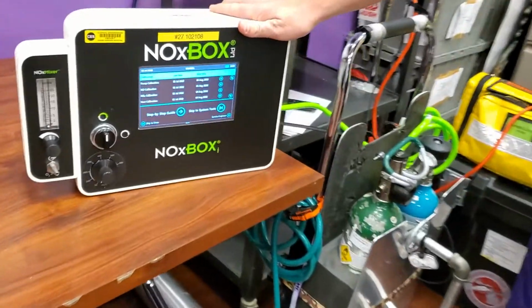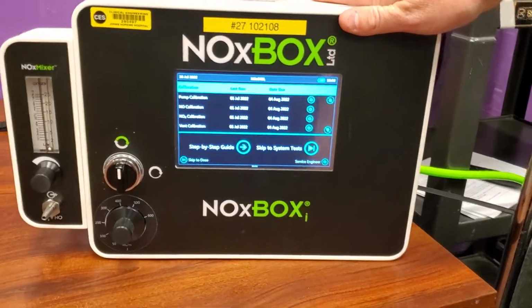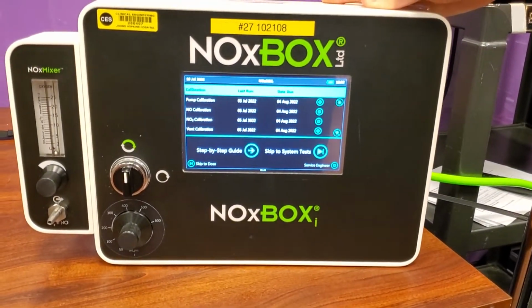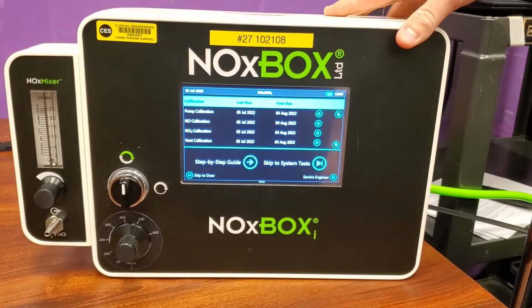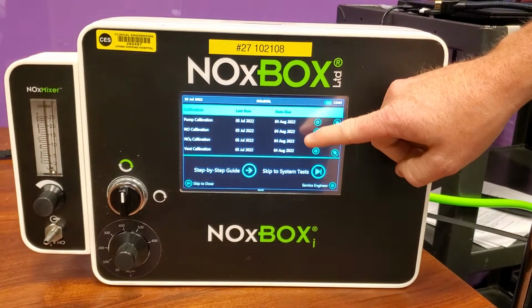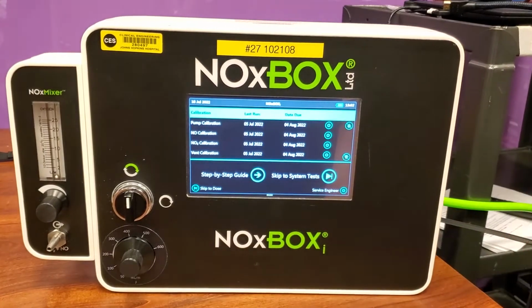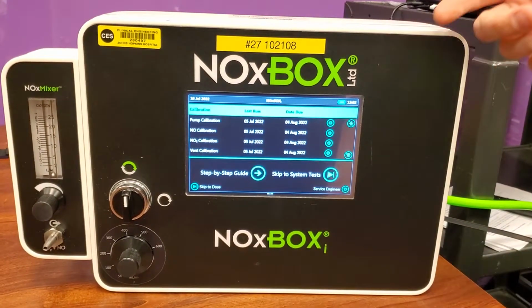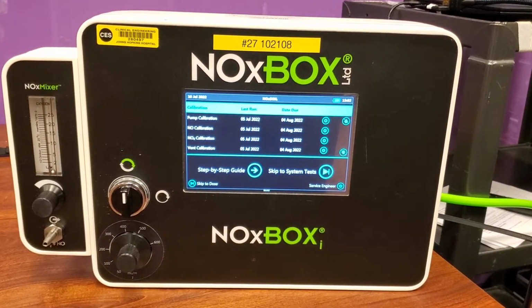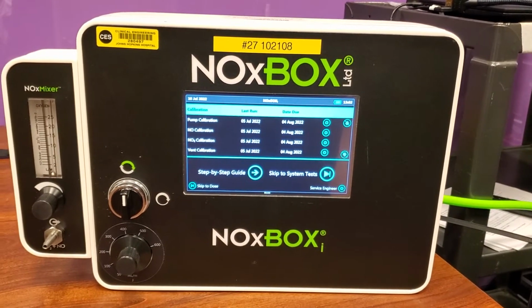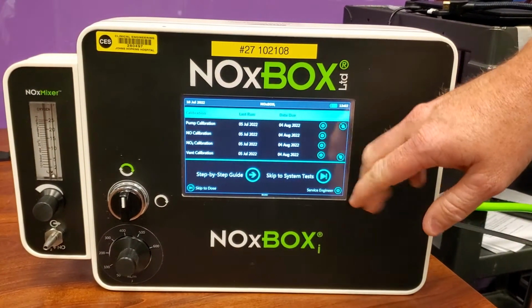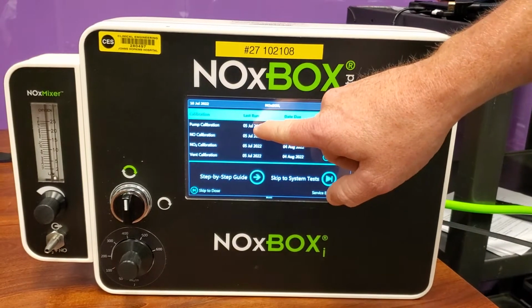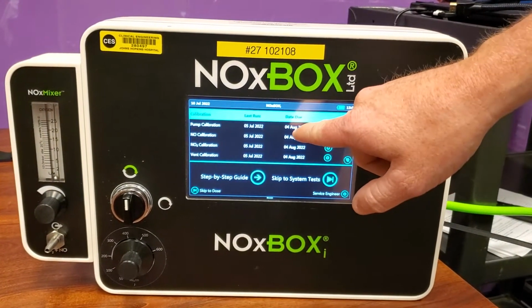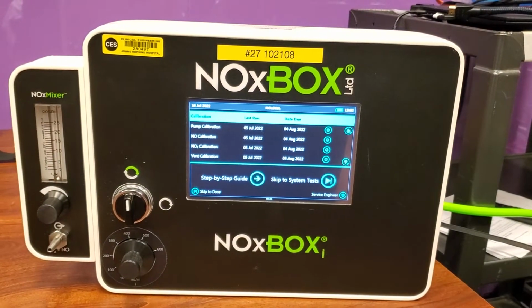So going back to our system tests and things here, we've gone through its self-test already, it's passed that, and then this brings you to your main home screen when you turn it on. There's a list of the most recent calibrations that have been done on it. We have had some issues in the past where people have turned it on and it shows that the high calibration needs to be done. So this can be verified here. We can see here the last time it was done was the 5th of July with a due date of the 4th of August coming up there.